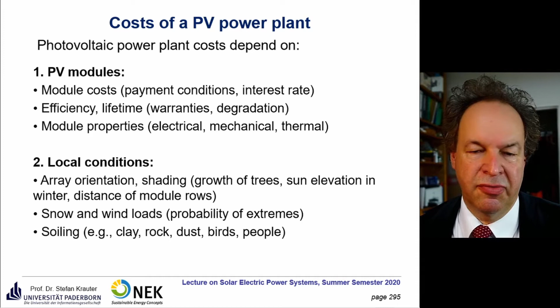Soiling is another factor — for example, if you install a PV power plant in the desert, there's soiling by dust or sand. Especially at southerly locations, where the module elevation angle is much flatter, soiling is more likely to stay on the module rather than be washed away by wind or rain. Birds can also cause soiling through droppings, and sometimes people may even throw debris on the modules. All of this has to be considered, with measures found to remove it.